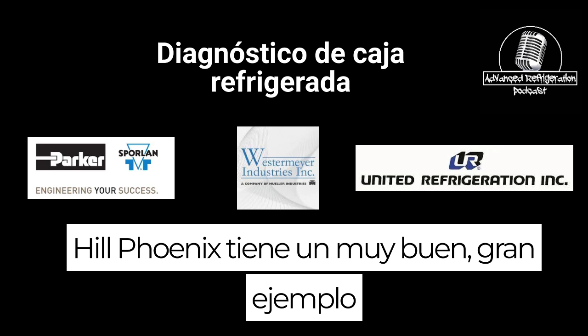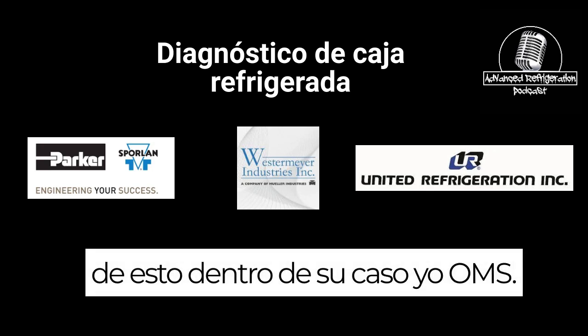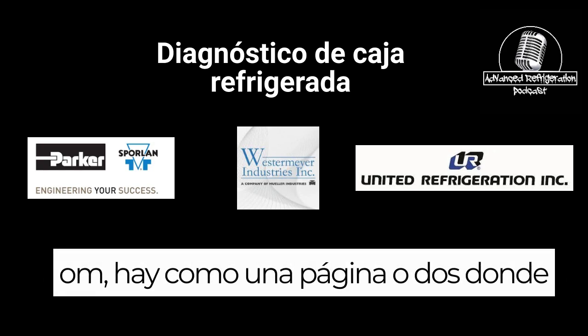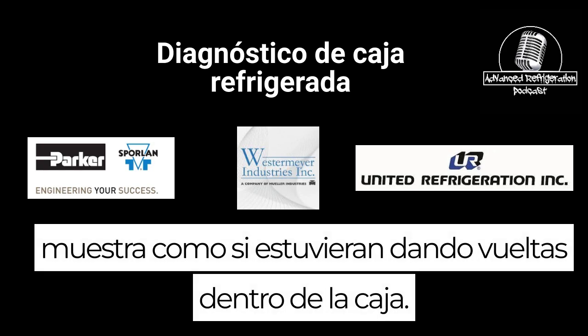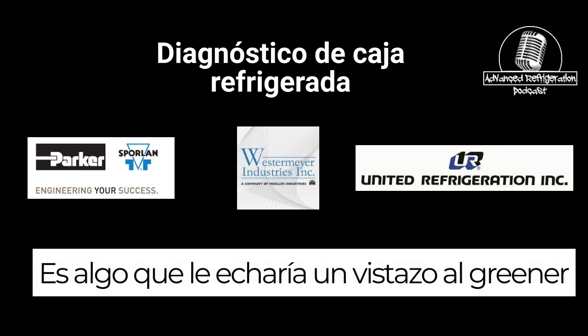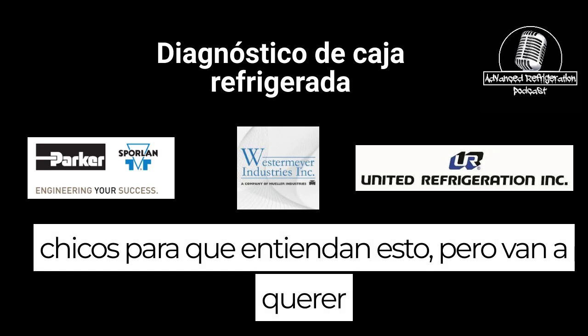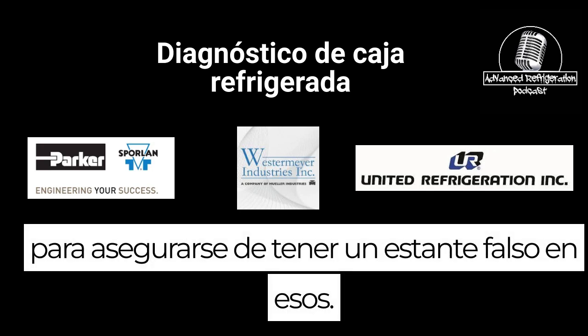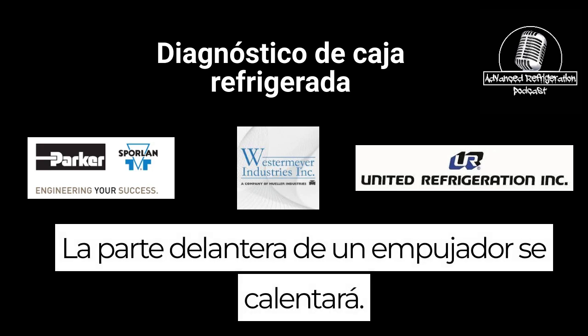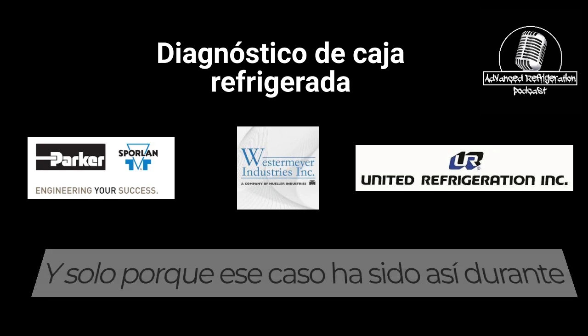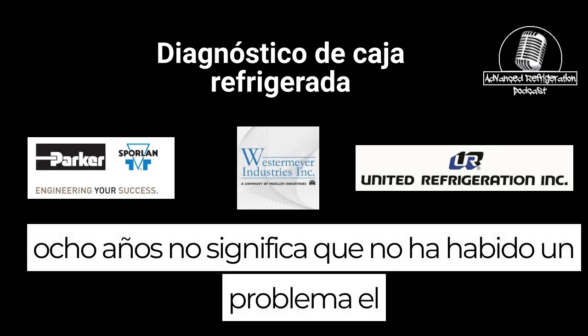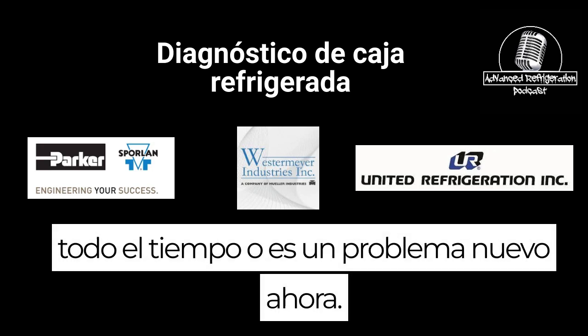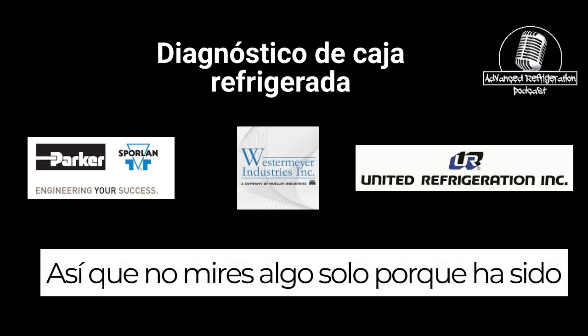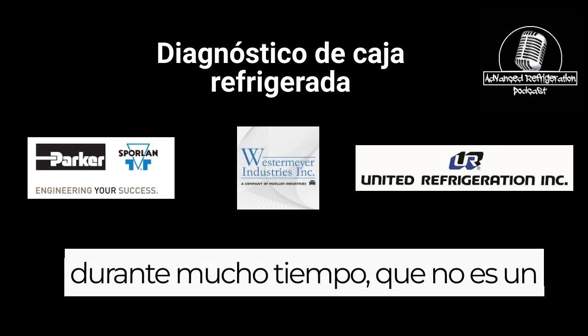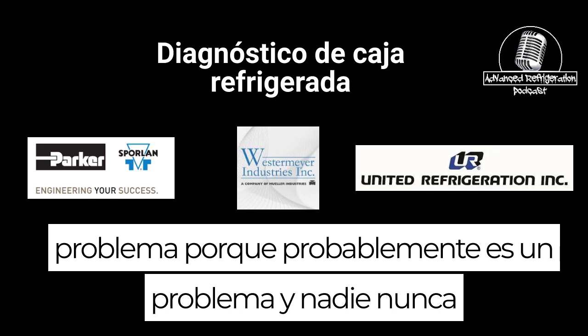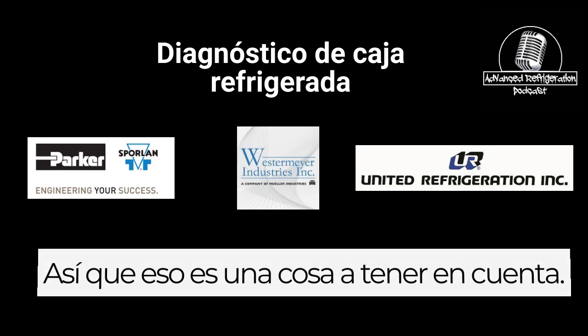Hill Phoenix has a really great example of this inside their case IOMs. I'm pretty sure it's just about every newer case IOM. There's a page or two where it shows the air swirling around inside the case. It's something I would take a look at. The greener guys may not understand this, but you're going to want to make sure you have a fake shelf on those. I see it all too often: the front side of a pusher will be running warm. And just because that case has been like that for 8 years doesn't mean there hasn't been a problem the entire time, or that it isn't a new problem now. So don't dismiss something just because it's been that way for a long time. It's probably a problem and nobody's ever caught it or done anything about it. So that's one thing to be mindful of.